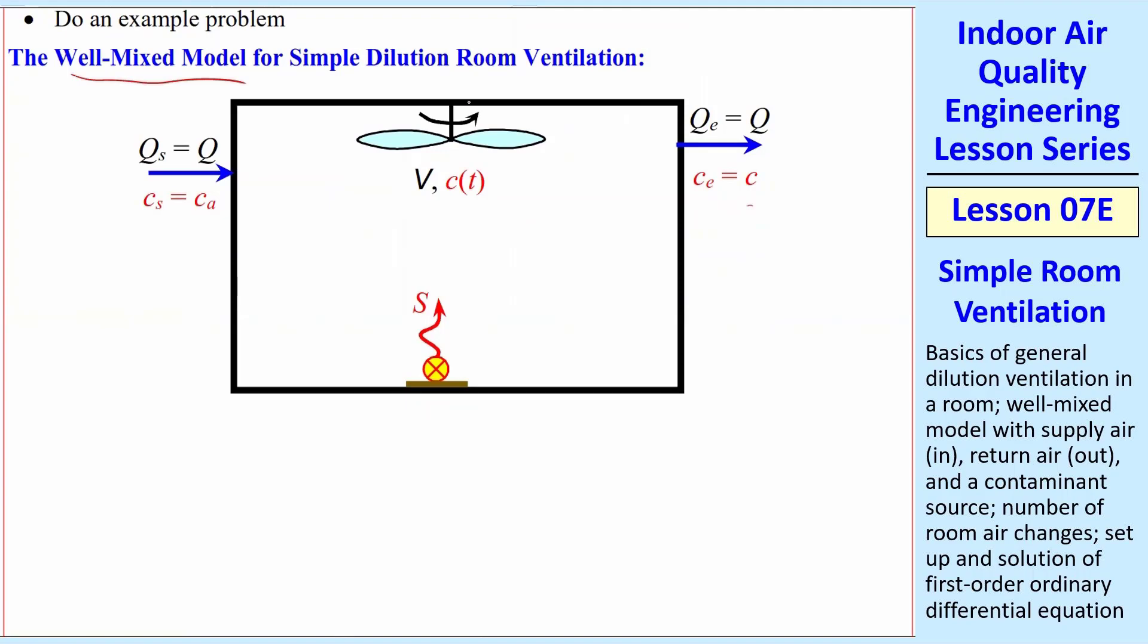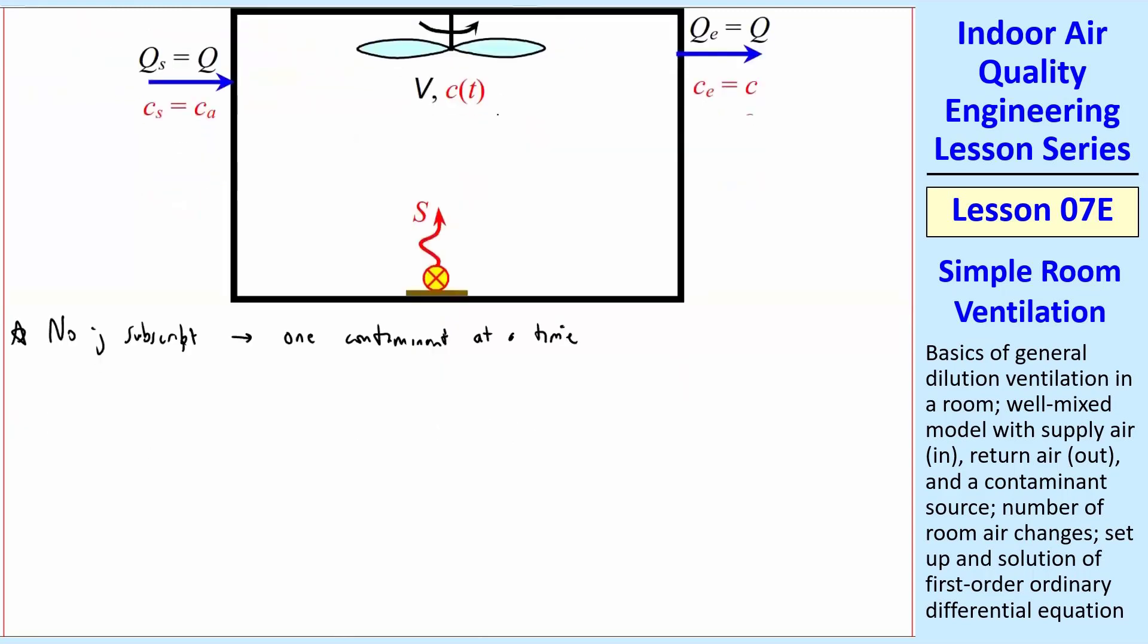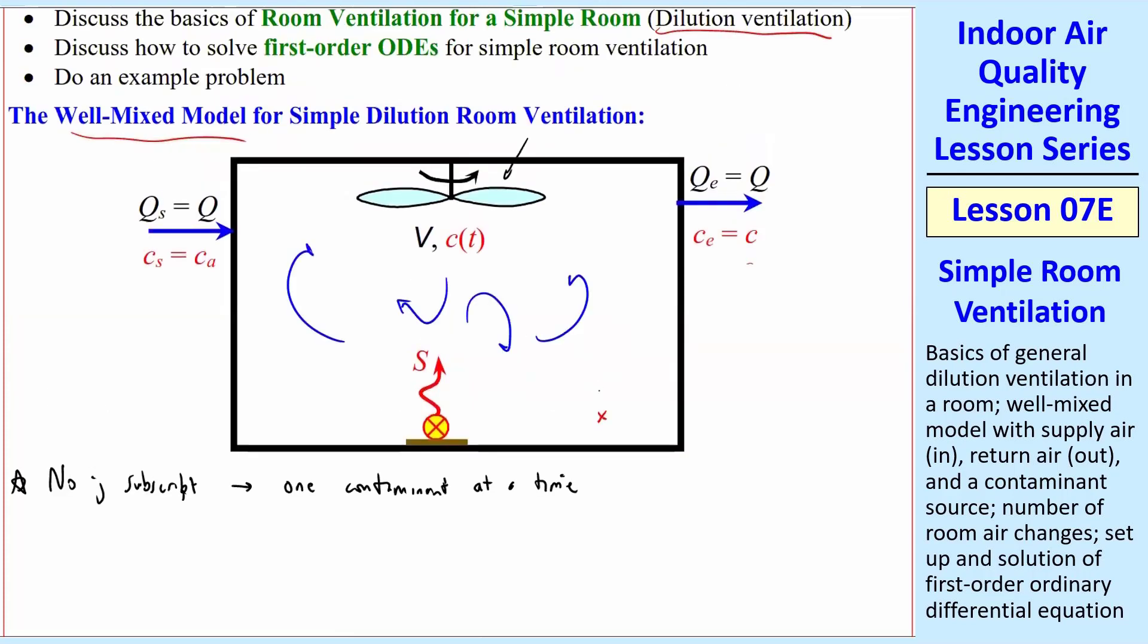Let's look at the well-mixed model. All we have in this room is some kind of a source of contaminant. We have a volume of the room, C, the mass concentration as a function of time. We have some supply air coming in that's at a certain concentration, Ca or Cs. And then we have exhaust coming out, which is also equal to Q. That's why I have this fan shown up here mixing up the air. That just means that the concentration here or here or here or here is all the same. So C is only a function of time.